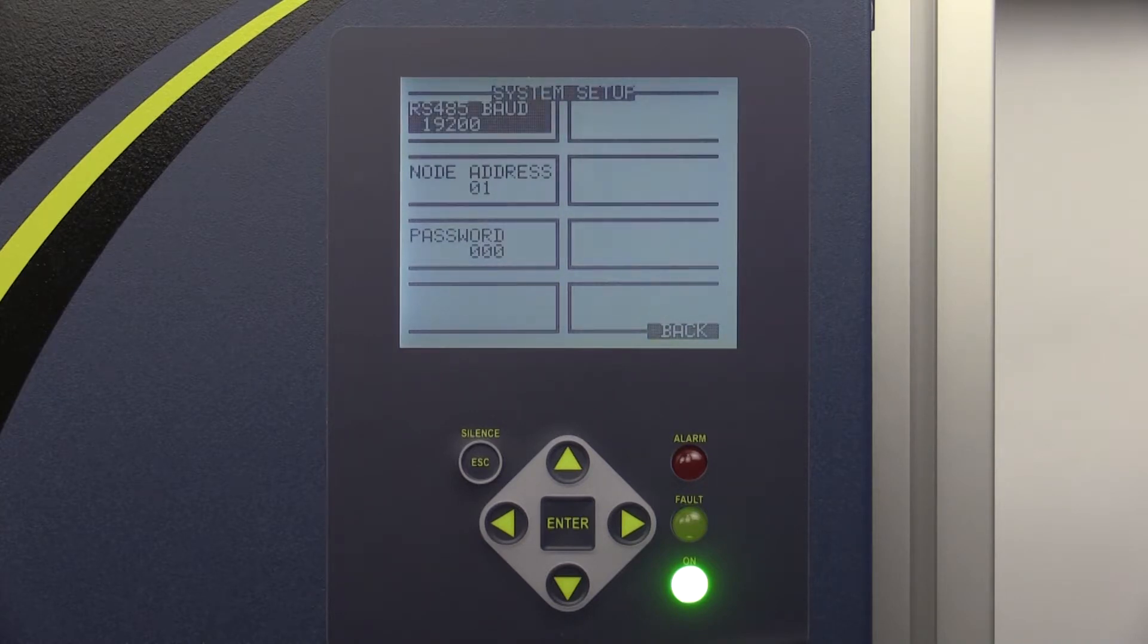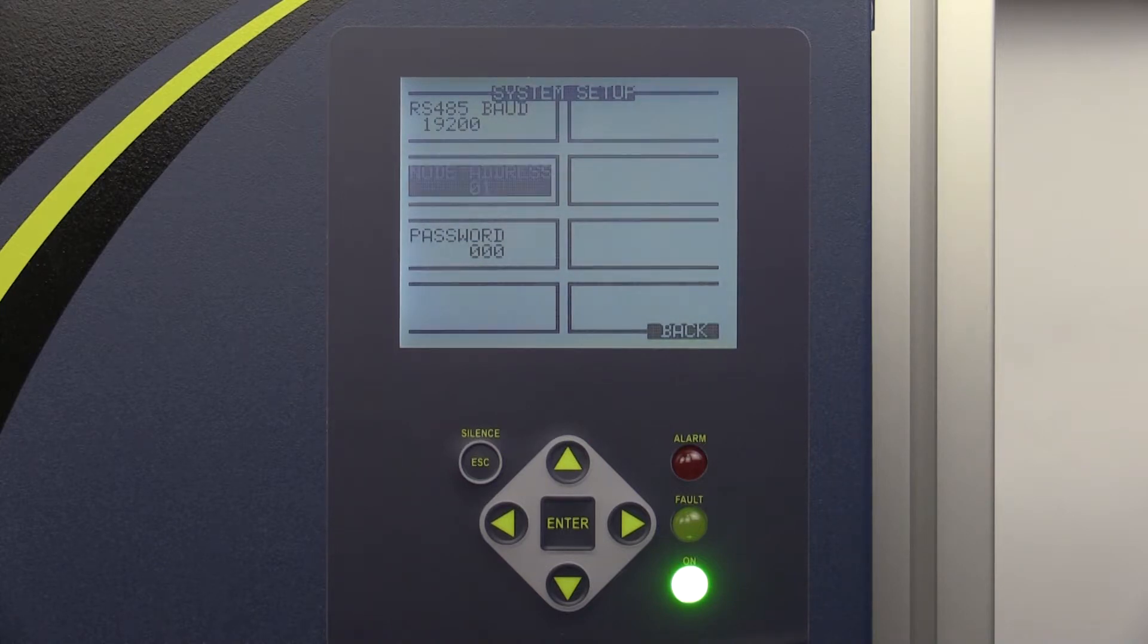The Baud Rate tab is used to set the baud rate for the RS-485 communication port. The default baud rate is 19,200, but there are several options to choose from. The Node Address tab allows you to set the distinctive node address of that specific monitor. Each monitor on the network must have a distinctive node address, which is set from 1 to 64.